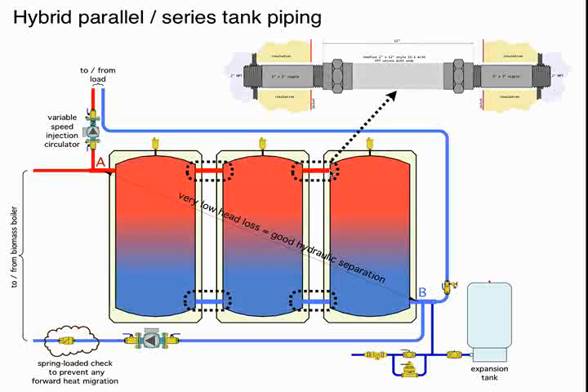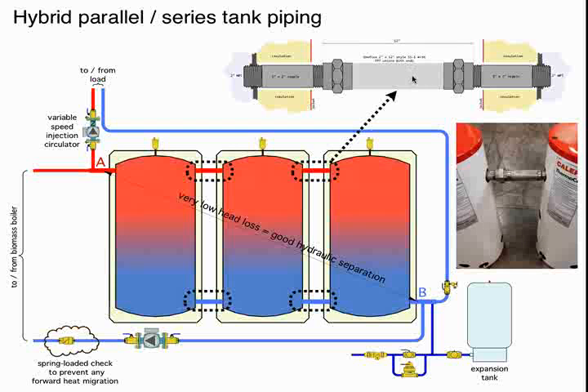But from a practical standpoint, we have to think how short can those be and still get these tanks to line up. And if you think about these tanks, there could be very minor variations in how these connections are welded into the tanks. There could also be variations in the flatness of the surface they're resting on. So to try to connect these with rigid pipe, especially large diameter, like 2-inch or larger rigid pipe, is going to be very difficult. So a short, flexible connector is a good option.